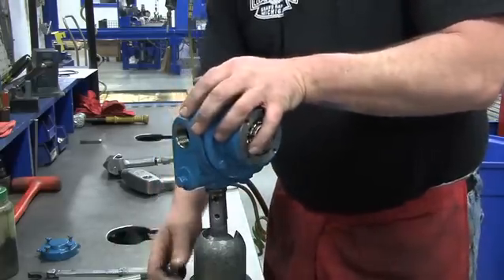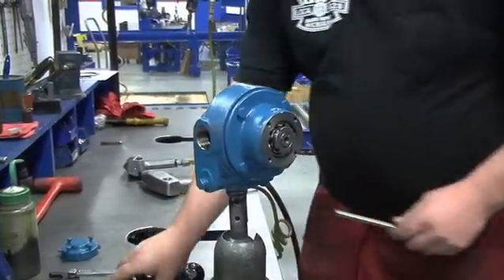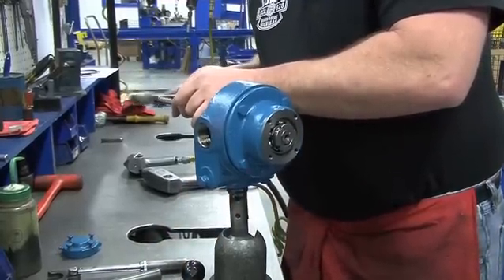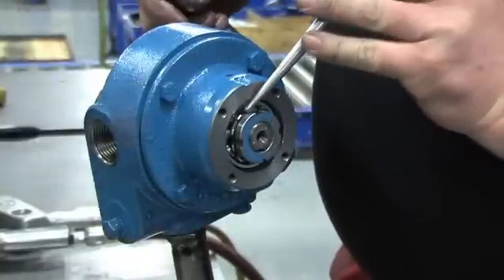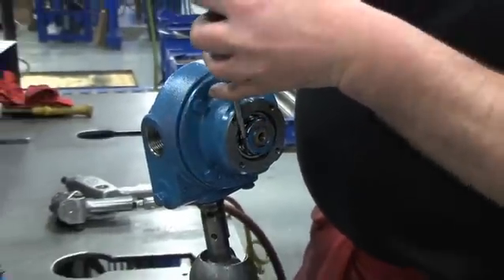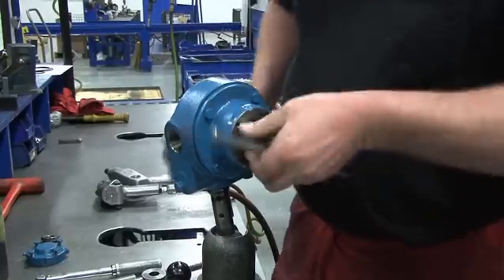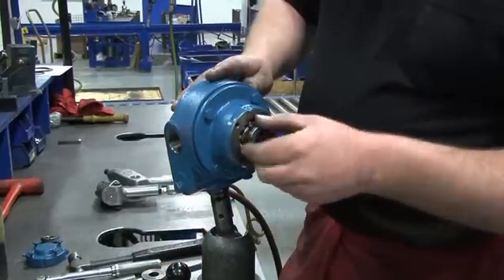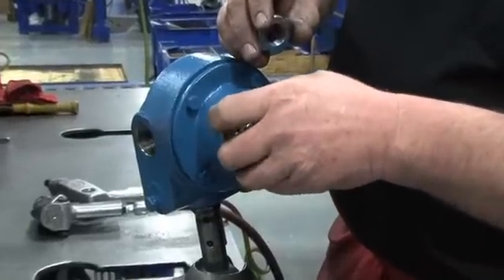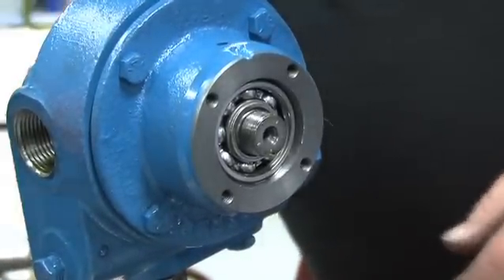On the shaft end protruding through the head, locate the lock washer and lock nut. Use a small hammer and punch to bend up the engaged lock washer tang. Insert the tip of the punch into one of the open slots of the lock washer. Using the hammer to tap the punch lightly, loosen the lock nut and rotate it counter-clockwise. Remove it from the shaft. Slide the lock washer off the shaft and inspect it for any damage. Remove the lock washer and the lock nut from the other side of the pump.